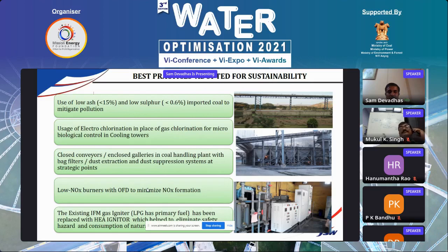And the conveyors, from the beginning of our yard till the gantry of our bunker floor, are fully covered, and we have installed bag filters at particular locations, as well as dust extraction and dust suppression systems at strategic points. And this is one of the modifications we have executed: the igniters, especially when we use oil firing. Earlier we used LPG as a primary fuel, so that has been replaced with a HEA igniter, which has helped much in eliminating the safety hazard as well as the use of LPG.